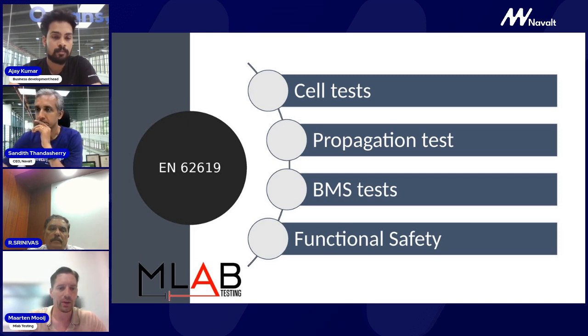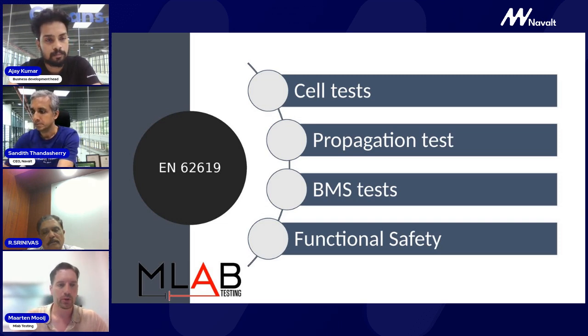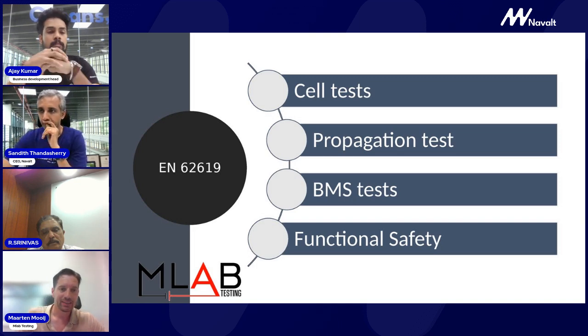But this is on cell level. The other test, there's an option. There's also a possibility to do the propagation test on the module level, and this is where you deliberately put a cell in thermal runaway conditions, either by nail penetration or overcharging, or maybe via laser to heat it up, or you can use heating pads.